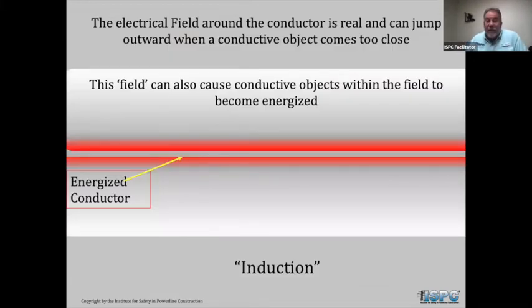All right, the electric field around a conductor is real. It can jump outward when a conductive object comes too close. Now, how far can it jump? A lot of it depends on the amount of voltage, the amount of current that's flowing in the line. This field can also cause conductive objects within the field to become energized. So we make sure that they know and understand and try to be able to determine for themselves when an induced voltage might be creating a risk to them while they're working. Even a pole ground, the copper ground wire coming down the pole, there's amperage always flowing on it because there's a return current.